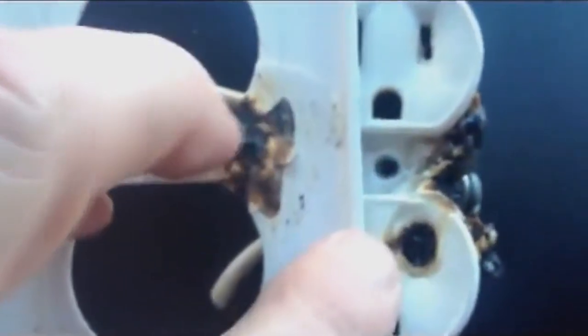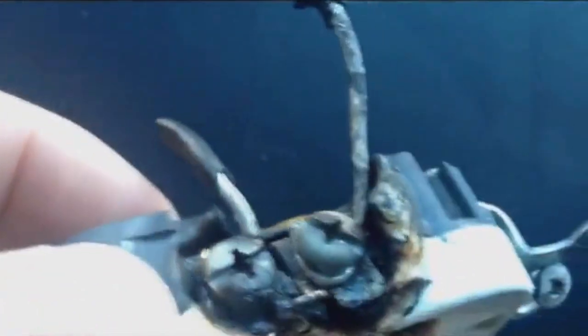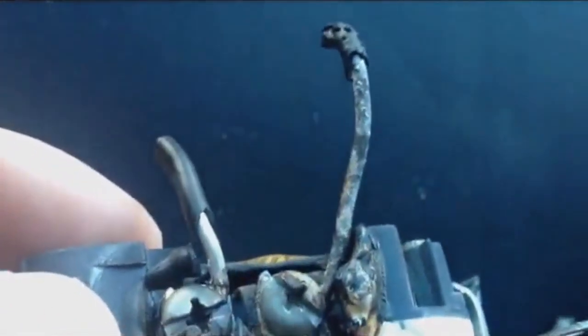This is real, this is burnt black. Here's the outlet itself. You can see the aluminum wiring right at the very tip — that very silver color we've been talking about. The silver is very evident here as well, except for the one on the right, which is burned.